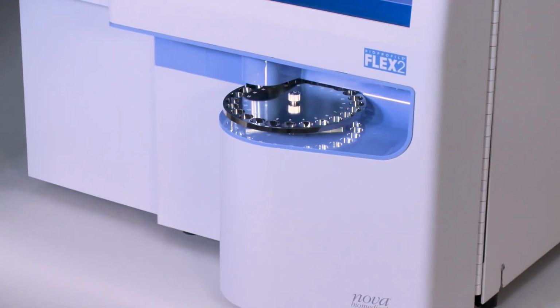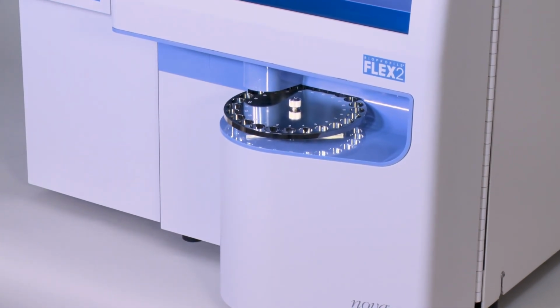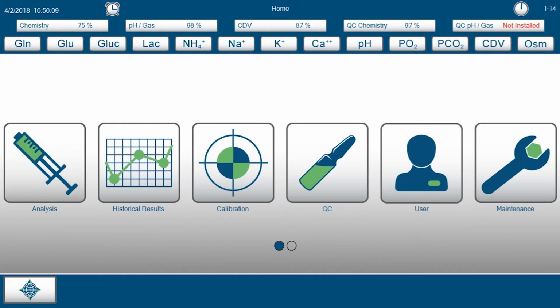If anything is changed, let's say a new reagent cartridge has been installed, the system will automatically populate the new RFID information and prime the new reagents. This smart maintenance will begin every time the analyzer door is closed, and a countdown timer icon will appear in the top right-hand corner of the user interface.